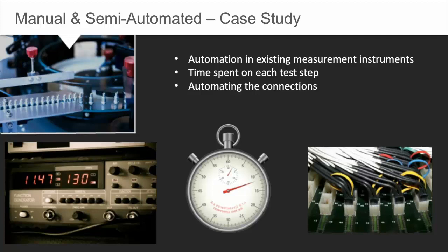Regarding the amount of time that the operator spent on each test step, the client had been through a lean assessment recently and had already done a good job timing the operations. However, we specifically noted the operator was manually connecting to the test points and manually transcribing to paper the measurement results from instrument displays. So finally, regarding automation of connections, this customer had so many different product models being tested at the one test system that connecting to the test equipment would be rather complicated. Either they would need many types of test harnesses, or they'd have to redesign their product to make the test connections more uniform. So after reviewing these findings, we made the following recommendations.